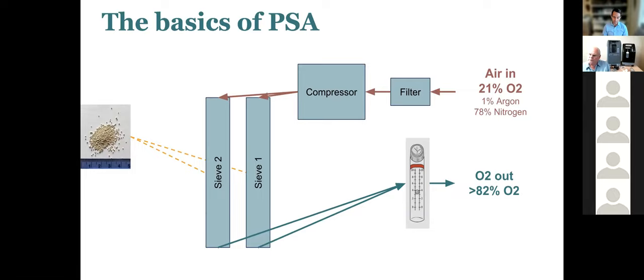And so the oxygen and also argon will pass through, and the concentrator will output a higher concentration of oxygen than went in. Now the concentrator will also purge the nitrogen out through a different channel that's not going to the patient. But what's coming out of the flow meter should be a higher concentration of oxygen. And generally the recommendation is this should be higher than about 82%.